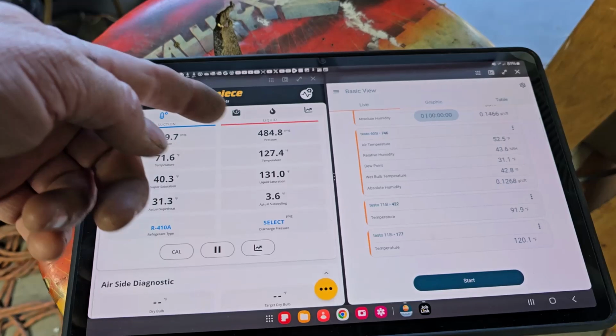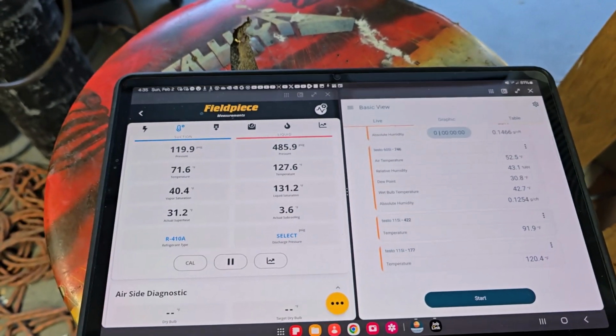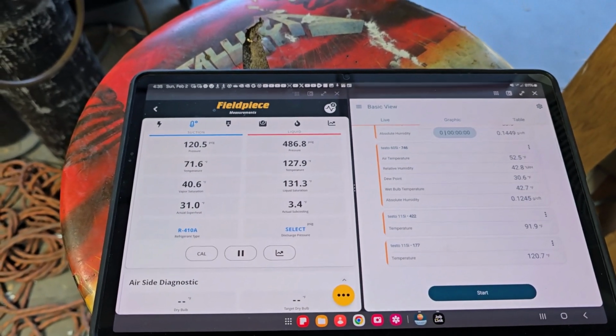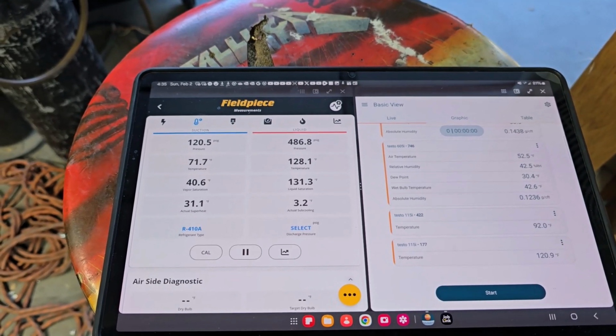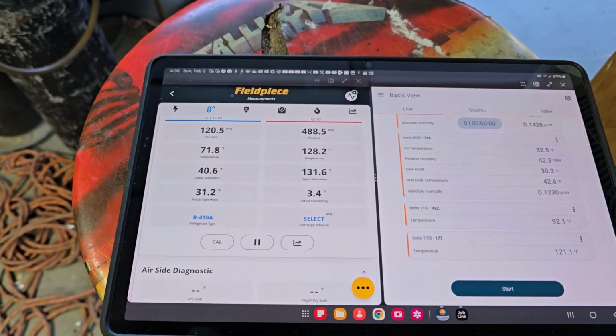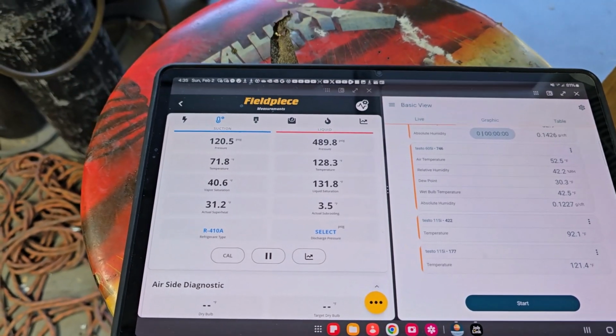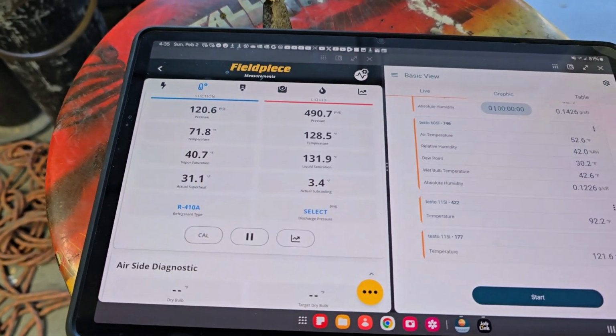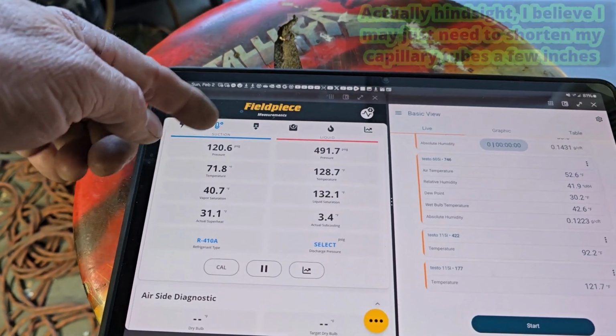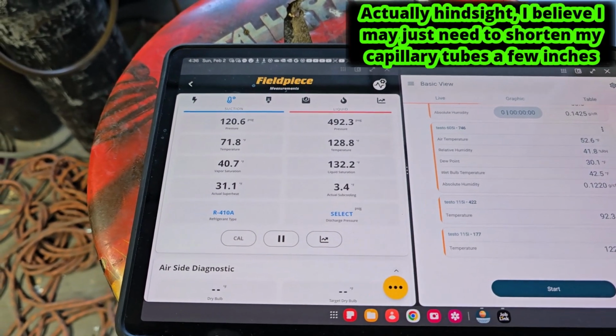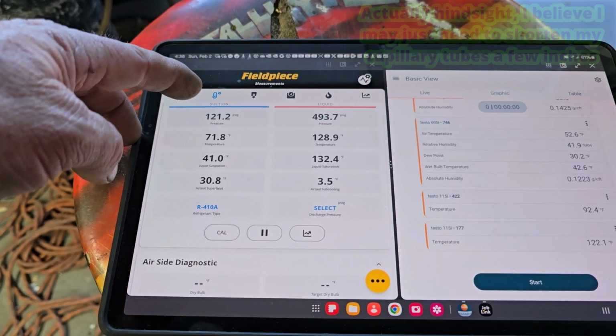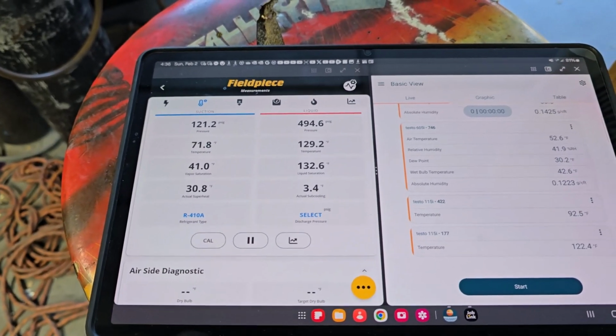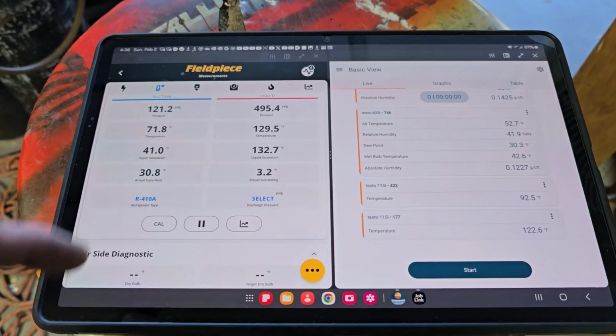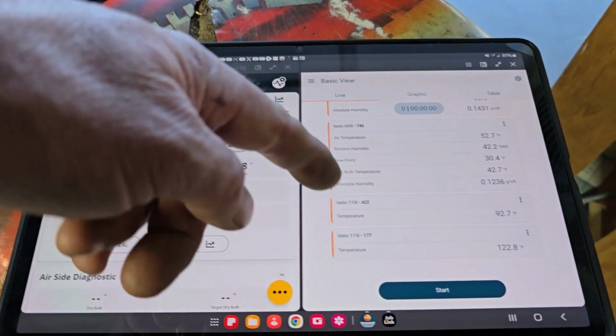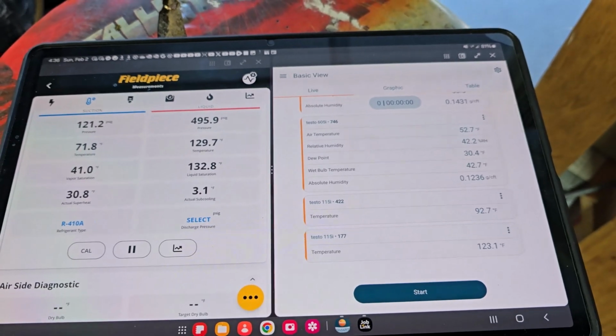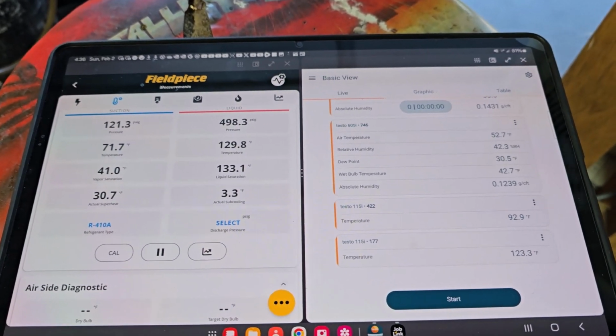The compressor's fully loaded, and we could calculate that compression ratio. I can already tell it's more than 3-to-1 because 150 to 450 would be 3-to-1, so it's probably pushing 4-to-1 right there. So it's pushing it a little bit. If I had a little more refrigerant, I'd probably get this up at this temperature, more to like 130ish or something, or even more. So I don't have anything hooked up to add refrigerant to it right now. So obviously that's going up, and if I had my automatic control, it'd be increasing the water pump speed.